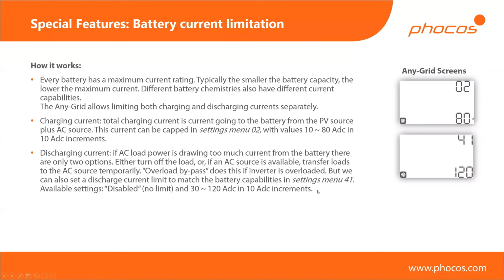Taking current out of the battery, obviously to power your loads, is a little bit more difficult. If you're in a pure off-grid environment and you have no AC source, so you just have PV, a battery, and your load, and you're exceeding the maximum current of your battery, there's no other energy source. If you're using PV, all of the PV power is piped automatically right to the loads. That's always the first priority. It's just the way the unit is set up. And then anything that's missing would come out of the battery. But if you're overloading your battery, discharging with more current than you can set up here, the only thing the inverter can do is shut down to protect your battery.